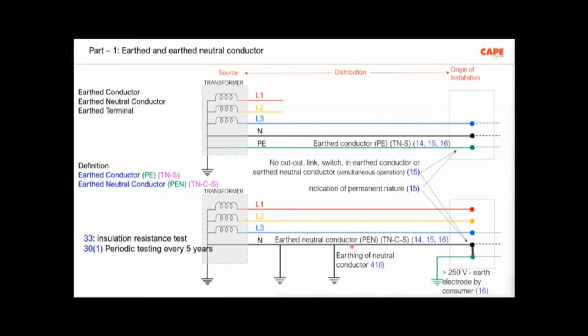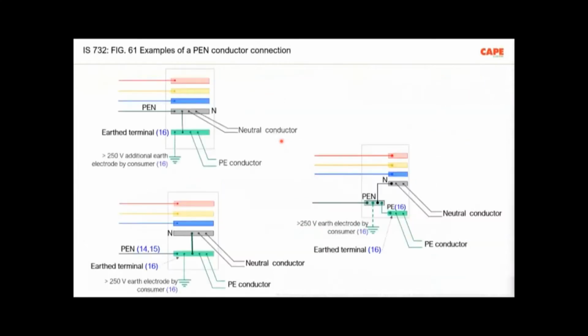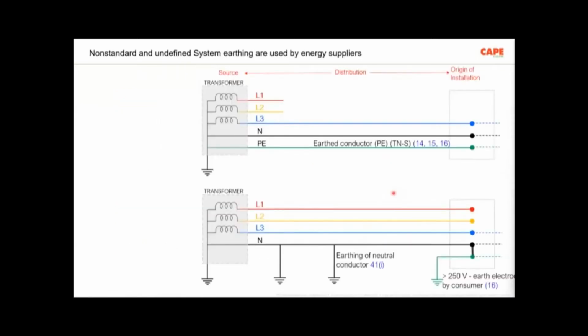So that metallic conductor fault return path is absolutely important, because in India, the electricity distribution company is giving you a cutout fuse, a porcelain fuse, and this porcelain fuse is supposed to protect our installation in case of a fault. And for this porcelain fuse, it requires a lot of energy to blow or to break, and that energy requires a lot of current, or enough fault current should flow to disconnect the supply. So these are very well documented in the regulations. Also, how to make the meter board is documented in several places, especially the REC documents, Rural Electrification Corporation documents. Since the 1970s, these documents have been in practice.